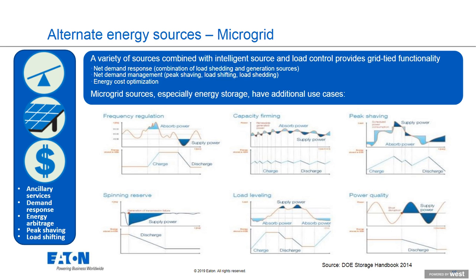The lower left shows something called spinning reserve. The utility company is required to keep some generators online but idle. They have to be running and synchronized, and if those generators' capacity is needed, suddenly they've got to spin them up, which takes a little bit of time—there's a ramp there. A UPS system with a battery could help support during that ramp instantaneously, without having to wait for synchronization or to start a diesel generator.